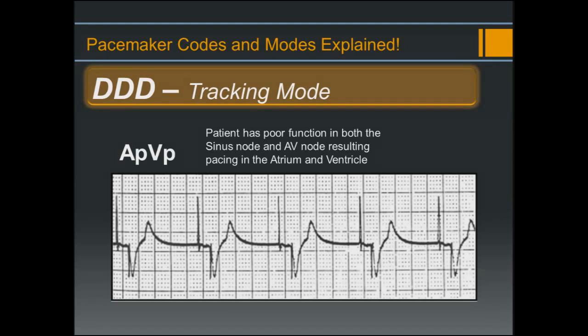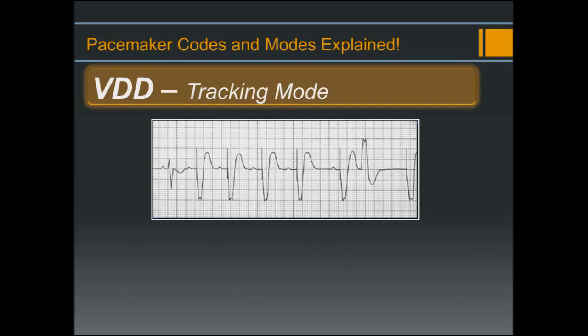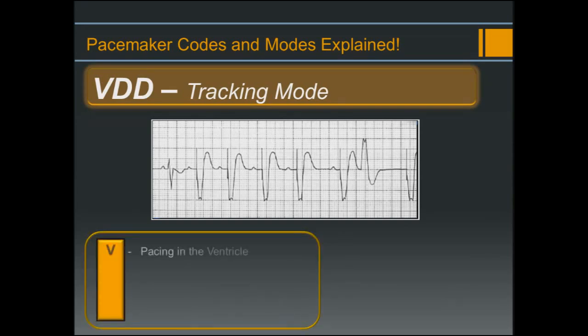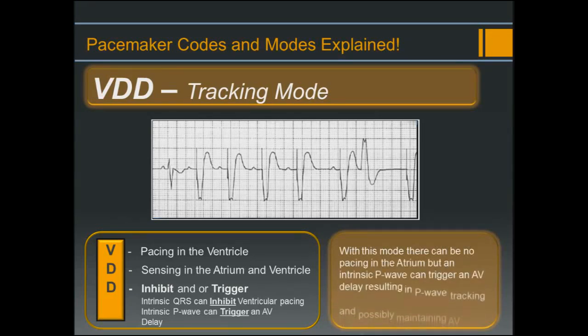Now let's move on to the second dual chamber tracking mode: VDD. With VDD, we are pacing in the ventricle, sensing in the atrium and ventricle, and the response to sensing will be to inhibit or trigger an AV delay. An intrinsic QRS can inhibit ventricular pacing, and an intrinsic P-wave can trigger an AV delay. With this mode there can be no pacing in the atrium, but an intrinsic P-wave can trigger an AV delay, resulting in P-wave tracking and possibly maintaining AV synchrony.